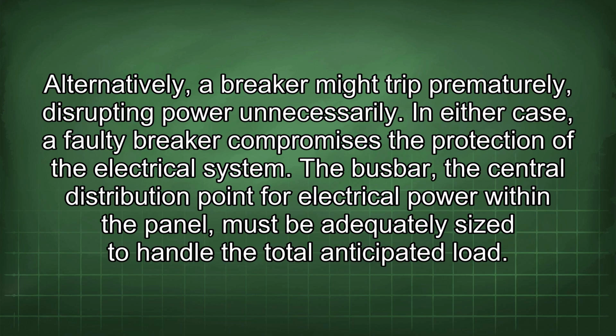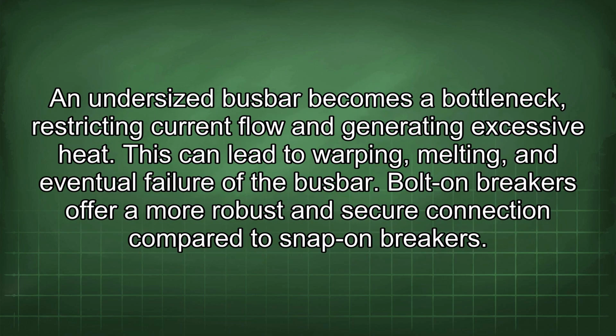The busbar, the central distribution point for electrical power within the panel, must be adequately sized to handle the total anticipated load. An undersized busbar becomes a bottleneck, restricting current flow and generating excessive heat. This can lead to warping, melting, and eventual failure of the busbar.